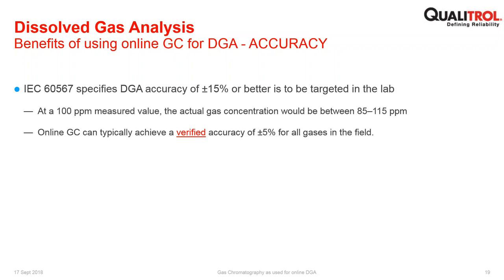Online gas chromatography, because you remove the whole element of sampling the oil and taking it to the laboratory, can typically achieve verified accuracy of plus or minus 5%. And verified is highlighted there because it is based off a calibration that has been performed in the very recent past and therefore can be considered verified.